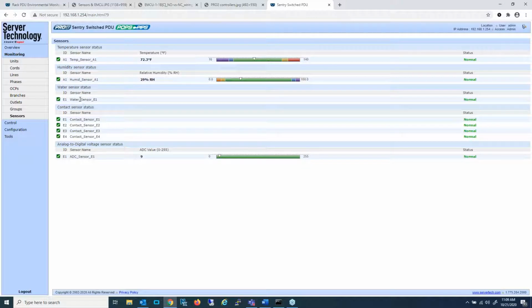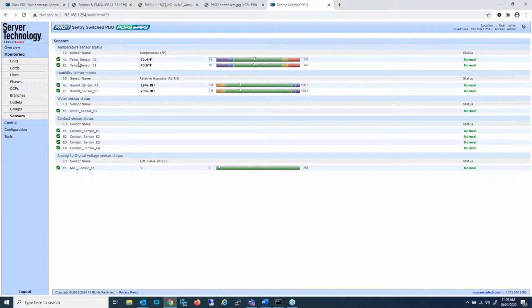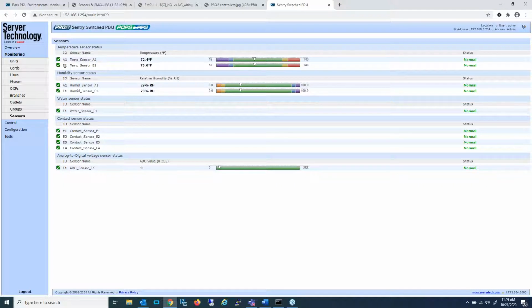We now see that it can recognize a water sensor, 4 contact closures, and an analog to digital channel. Now I will attach a second temperature and humidity probe, in this case a Gen 2 sensor, to the environmental monitor control unit. And upon refresh, we now see that I have 2 temperature sensors and 2 humidity sensors. So A1, A is the parent PDU. 1 means that the sensor I've attached is on the TH1 port. E is always the indicator for the environmental monitor control unit. We can see that over here in units.